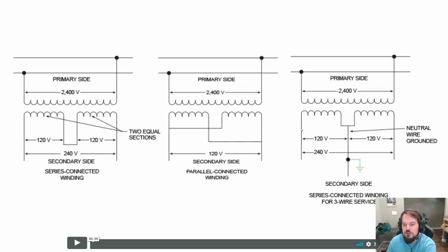So if you read from here to here, you are reading just the 120 volts off of this coil. If you read from the other hot to the neutral, you're reading just the 120 volts from the other coil. If you read hot to hot, you get the 240 volts, which is the 2 120 volt coils added together.